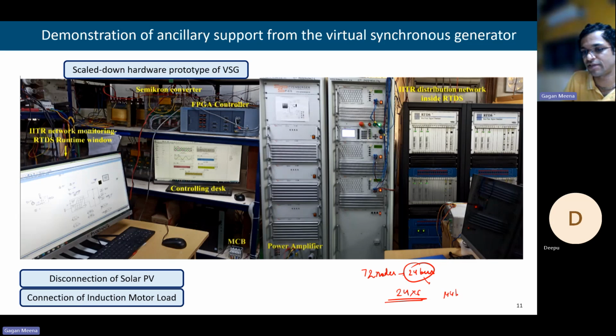We can simulate 24 multiplied by total 6 - a 144 bus system can be simulated on 6 racks. On one rack we can have a 24 bus system, so we can have this 144 bus network within the RTDS across 6 racks.